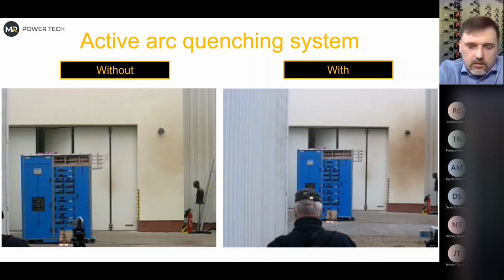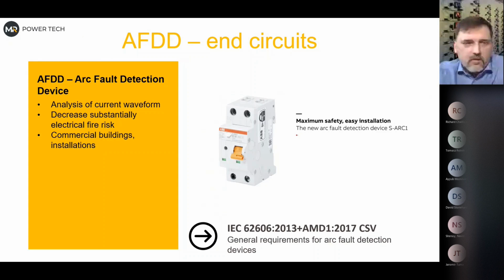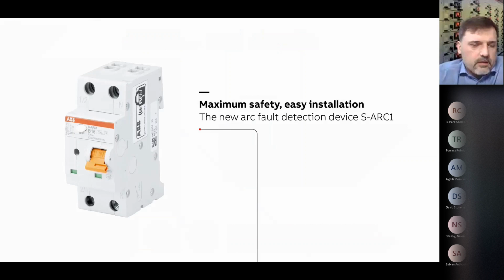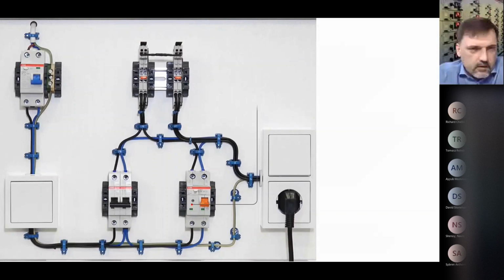And there is one thing that I would like to put aside here. It has the same name. So we have arc fault detection devices, which are, for some time already, mandatory in commercial installations, depending on the country you are in. It has a similar name, but it serves a different purpose. So you see the words arc fault, arc flash, but it's something different. I picked one from ABB because I like the way they make it, just to give you an idea what it is. So we use it in commercial buildings, but the purpose is different.